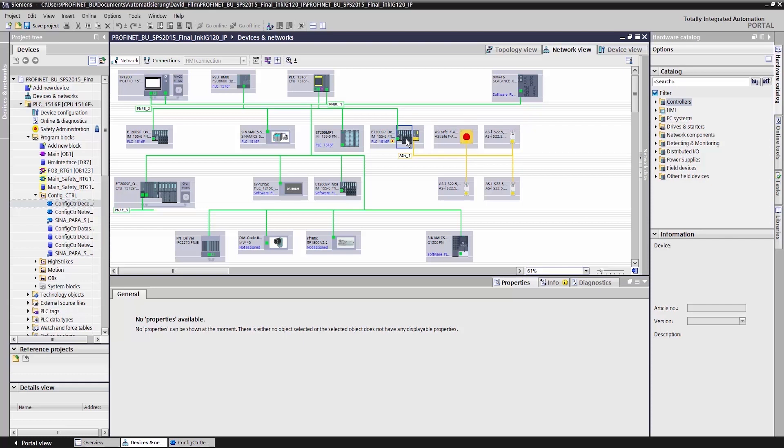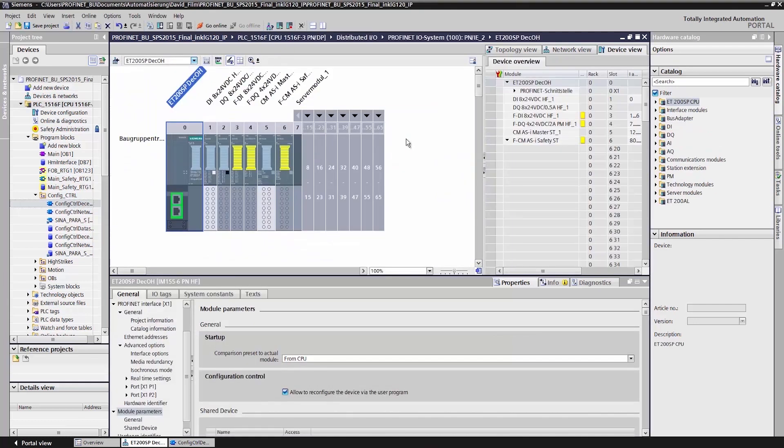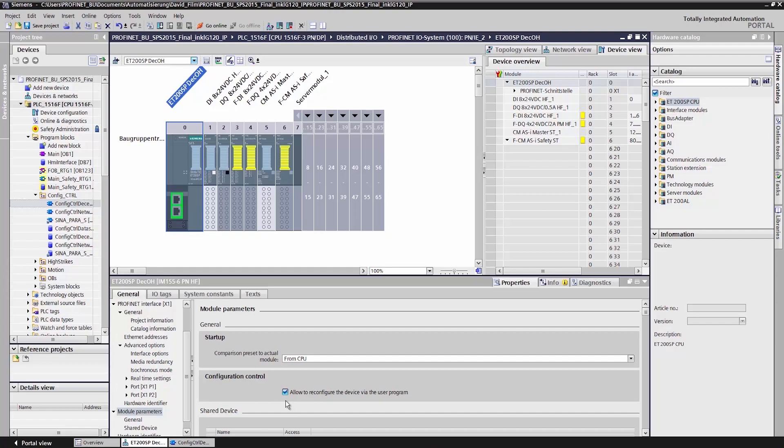In the hardware configuration, shown here in our example with the ET 200 SP, I activate the checkbox Enable Reconfiguration of the device via User Program in the Module Parameters section.